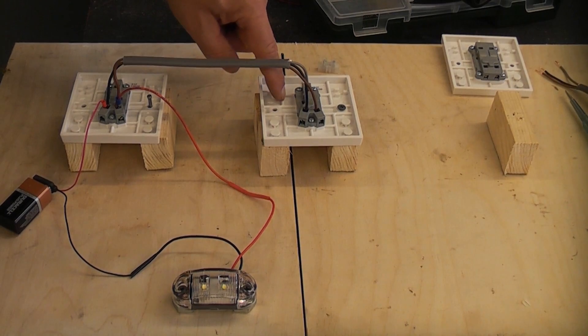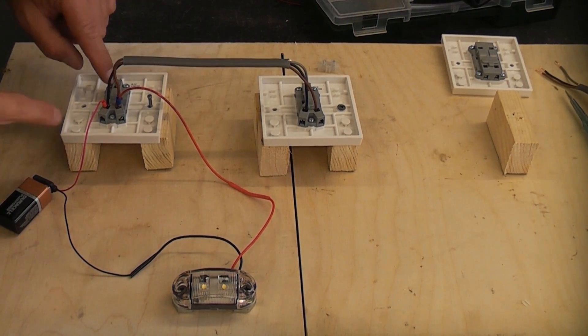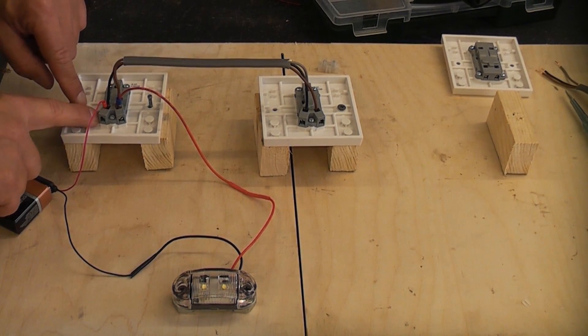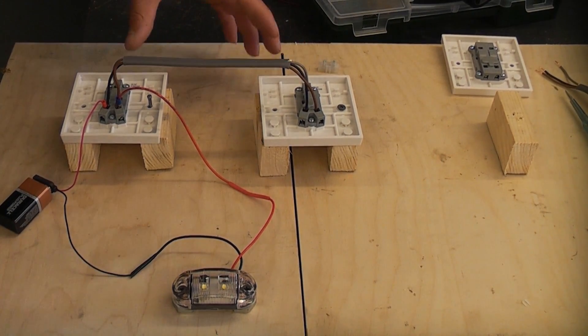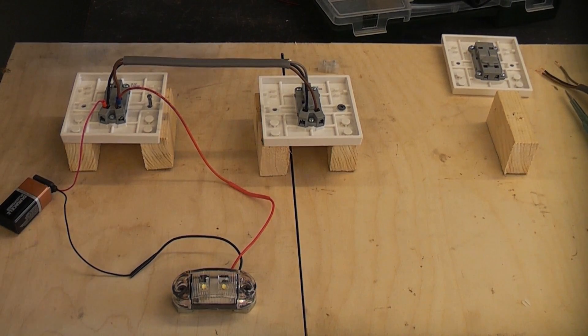These two switches are both two-way switches so they both have a common, an L2 terminal, and an L1 terminal. If you wanted to add another switch to this to make it three-way or even more than three-way, you can put as many intermediate switches as you want in a circuit like this.